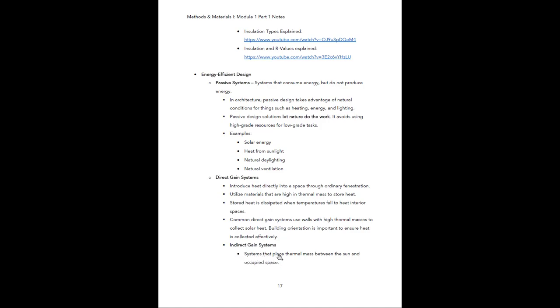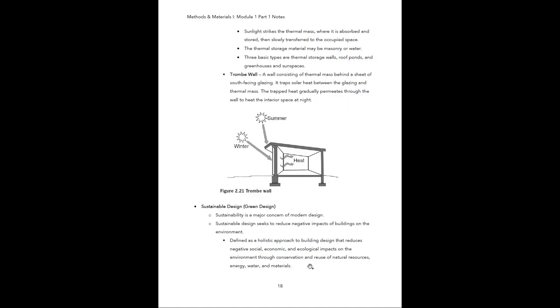Indirect gain systems place thermal mass between the sun and the occupied space. Sunlight strikes the thermal mass where it is absorbed and stored, then slowly transferred into the occupied space. The thermal storage material may be masonry or water. There are three basic types of thermal storage approaches: thermal storage walls, roof ponds, and greenhouses or sun spaces. A Trombe wall consists of a thermal mass behind a sheet of south-facing glazing. It traps solar heat between the glazing and thermal mass, and the trapped heat is gradually permeated through the wall to heat the interior space at night.